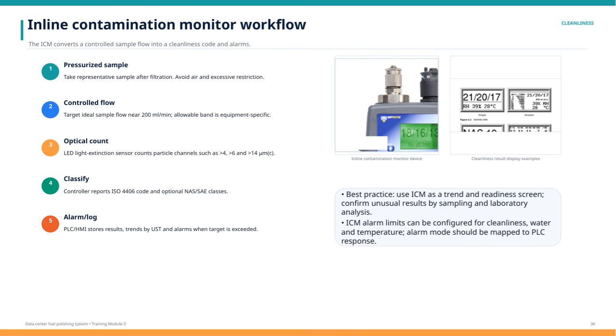Next, the flow is carefully controlled, ideally near 200 milliliters per minute, although this target can vary depending on the equipment used. The core of the process involves optical counting. The ICM uses an LED light extinction sensor to count particles in different size channels, such as those greater than 4, 6, and 14 micrometers. This allows precise measurement of contamination levels.